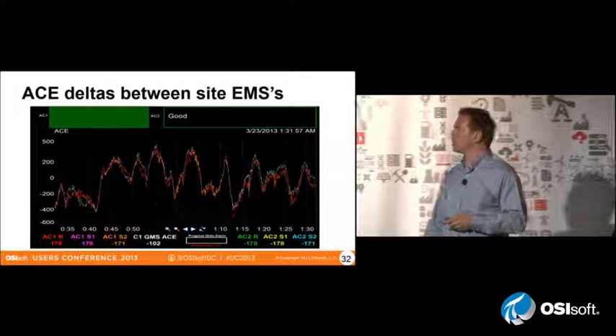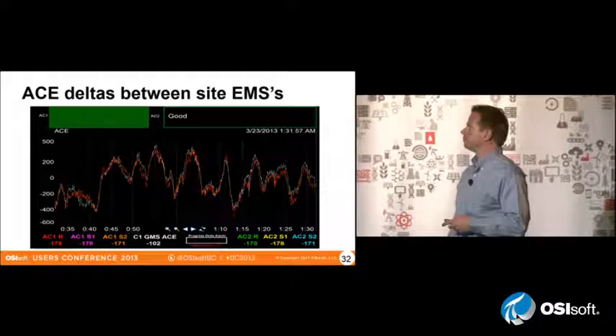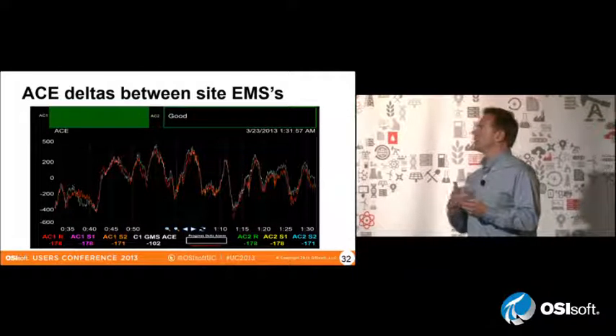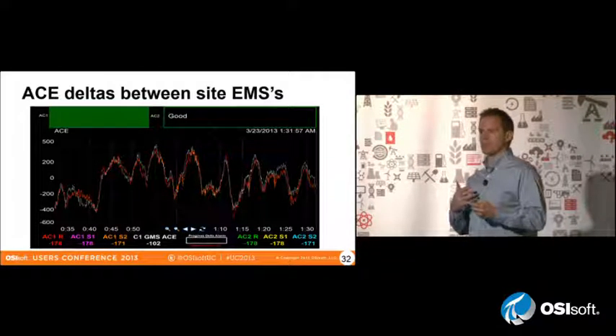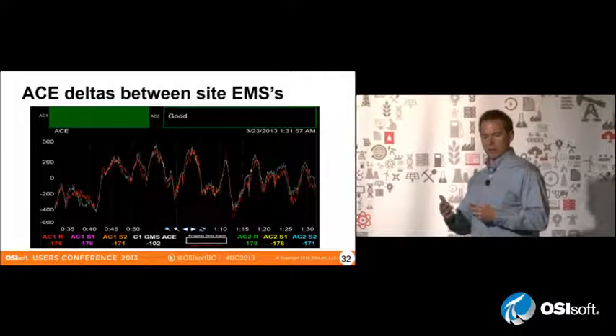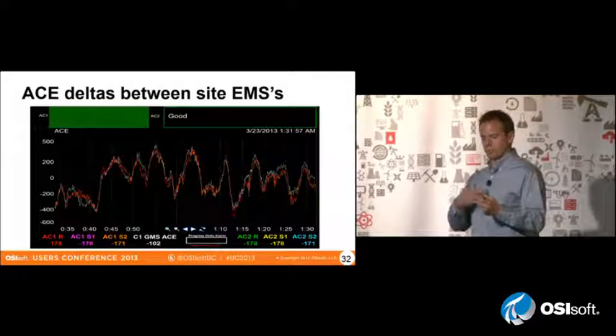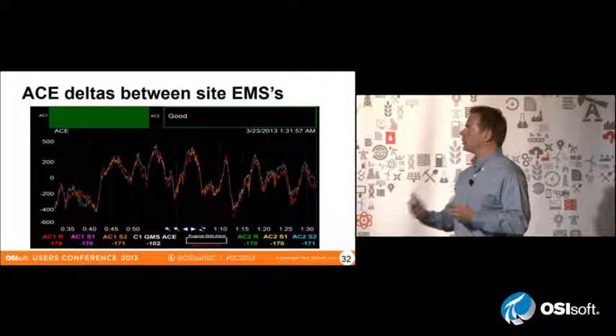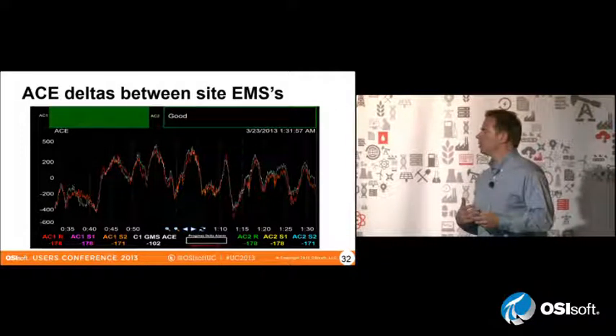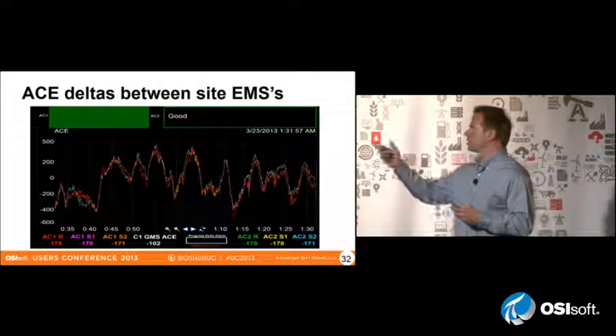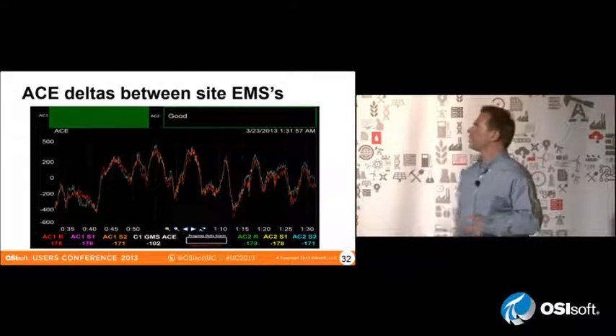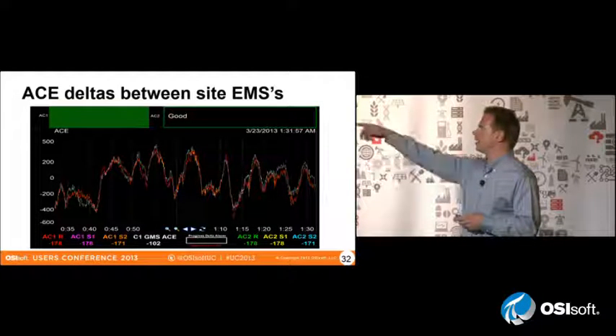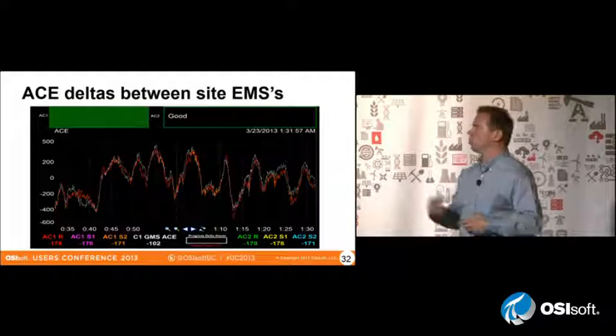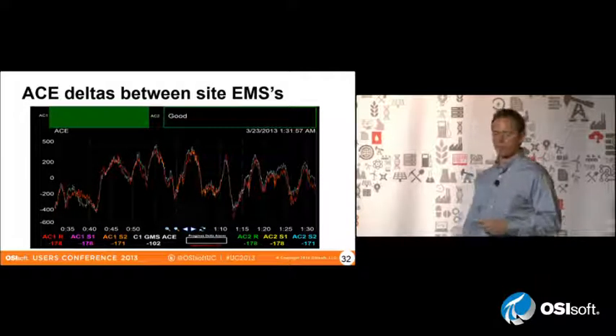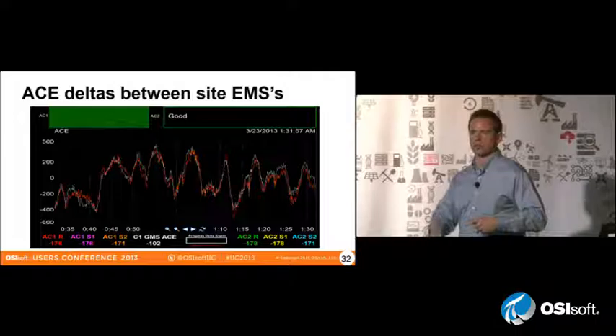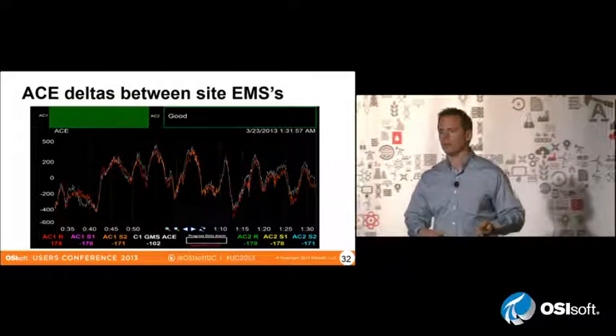This display overlays the ACE from each of our EMSs and also our backup GMS. If all the ACE are tracking on top of each other, we know all the data is good. If we get a spike in one of these trends, the indicator on the top left, which normally says good, will turn from green to red and tell you which EMS has bad data. We have to make sure our GMS and both EMSs always have good data in case we have to switch from one to the other.